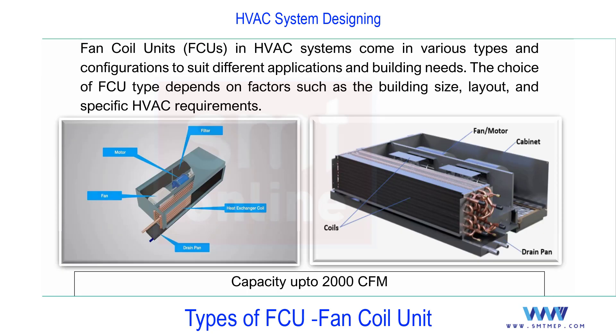The components of an FCU are simple: a heat exchanger coil (evaporator for cooling, heating coil if connected to a boiler or VRF), a fan with motor inside the casing — one or two fans depending on capacity — and filters. If it is a two-pipe FCU there are two pipes; a four-pipe FCU has four pipes for separate heating and cooling circuits.